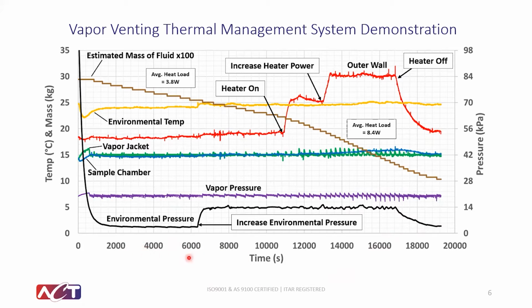Everything here is plotted against time. This whole experiment lasted roughly 5.5 hours. The sample chamber and vapor jacket temperature are indicated by the blue and green line respectively. The goal of the experiment was to maintain the sample chamber temperature at the target 15 degrees C throughout the entire experiment. The environmental temperature, indicated by the yellow line here, we can see was roughly 9 to 10 degrees warmer than the sample chamber. So this provided a constant heat load from the environment to the prototype.